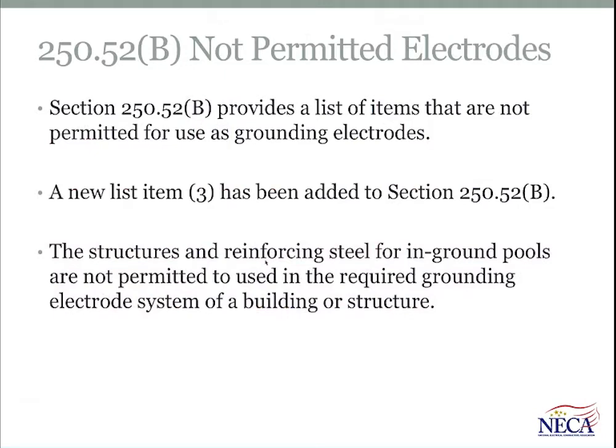This is the one I started talking about before in 250.52A. Section 250.52B has a list of electrodes or metal components that are not permitted to be used as electrodes. And we know aluminum is in that list. We know gas piping is in that list. What joins that list is a new item 3, and it clarifies that structures and reinforcing steel for in-ground pools are not permitted to be used in the grounding electrode system for a building or structure.